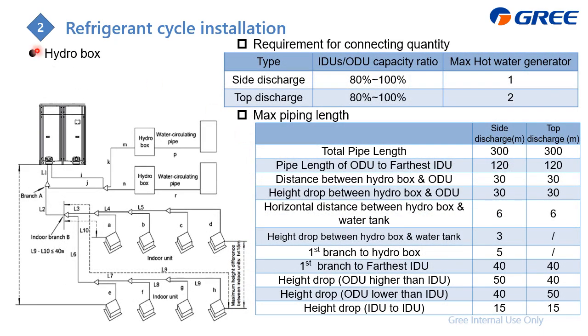When you adopt the hydro box, just follow this diagram to install it. For this one, for side discharge and also top discharge, the piping limit is a little bit different. Just pay attention here. For the others, it's almost the same. Also, you can rely on the VRF selector to have a double check.